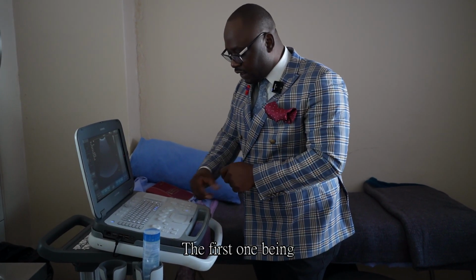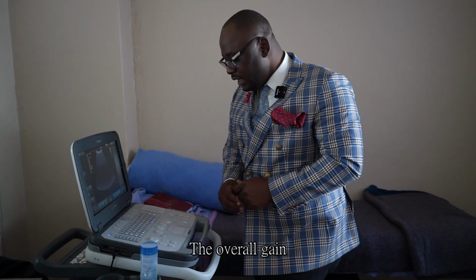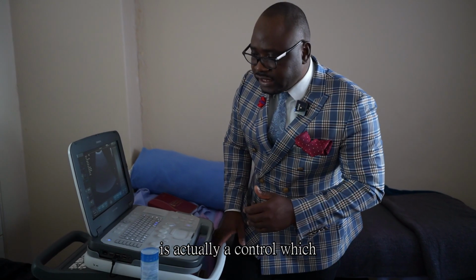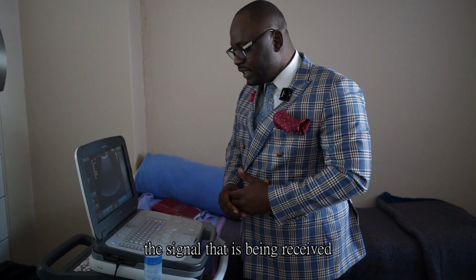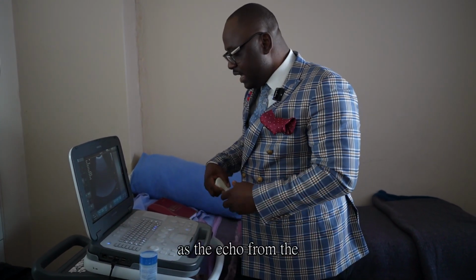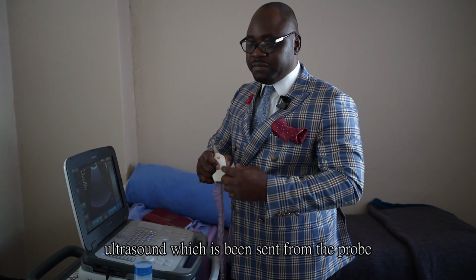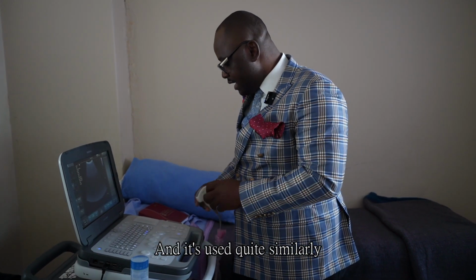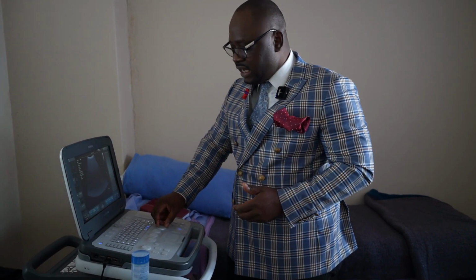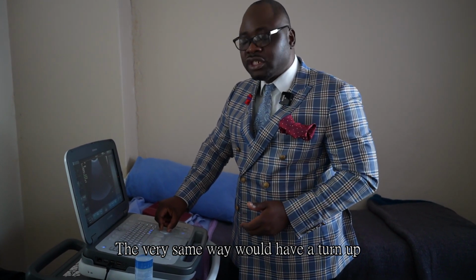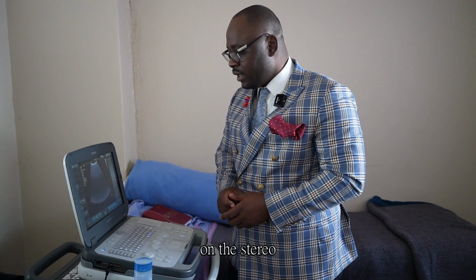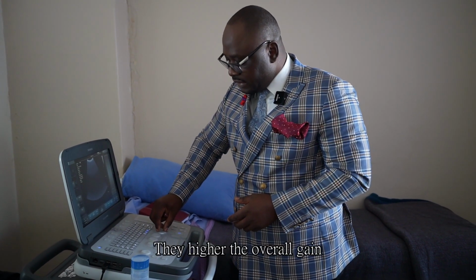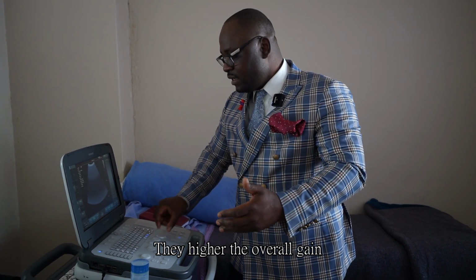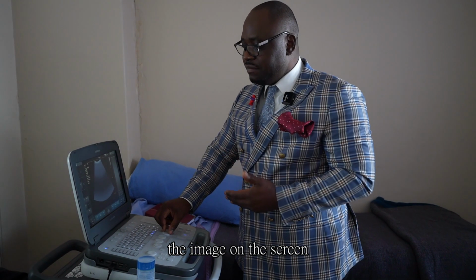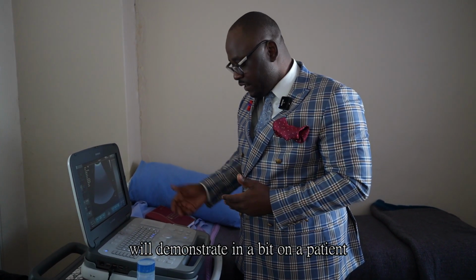The first one is the overall gain. The overall gain is a control which helps to amplify the signal that is being received as an echo from the ultrasound which has been sent from the probe. It's used the very same way we would turn up the volume on a stereo. So the higher the overall gain, the brighter the image on the screen. We'll demonstrate it in a bit on a patient.